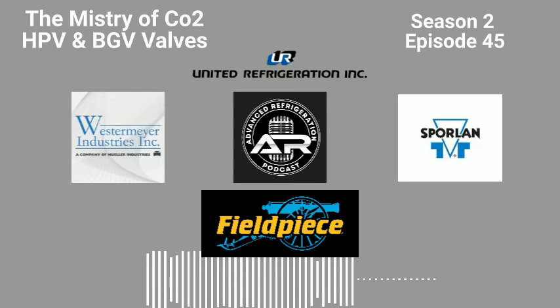Go ahead, Brett. So since you're talking about, we moved on, unfortunately, but I just thought of something. Let's discuss the placement, because yes, we know that there's a controller, either a Danfoss, iPro, whatever, hooked up to control the HPV and the BGV. But where is the sensor placement? I believe for the HPV, the sensor needs to be right on the drain leg, right? 12 inches out from the bottom. And the same thing with the sensor, with it insulated, and they also recommend that you seal it up with reflective tape to make sure the weather doesn't hit it, right? So the sensor, usually 6 inches.